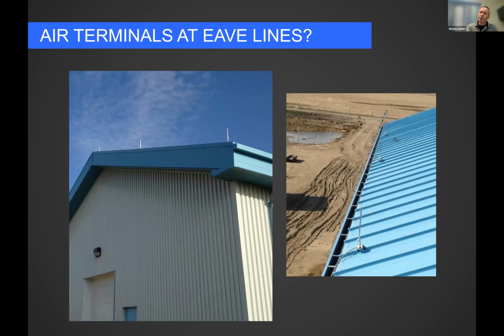This is one you probably won't see a lot. Eave lines above 15 meters tall are required to have lightning protection. This particular building's eave lines weren't quite that high, but I wanted to show what air terminals at an eave line look like. The reason is that even on sloped roofs you can protect with just a line of lightning rods down the middle, if the slope is over a certain amount.